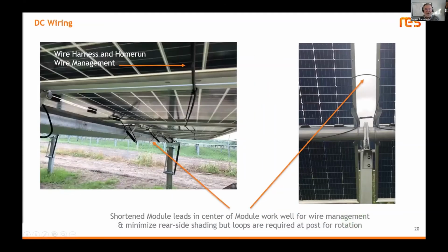There are a couple of pictures that I want to show here. For example, you have to understand the home run, the wire harness home run. Where does it go? Can it go like this on the rear side of a module? Or this? You have to plan for it. There's no room for improvisation. It needs to be validated. The shorter leads, if you have junction boxes, are definitely a benefit, but because you have a moving part, that lead needs a loop at the post, where the posts are, to allow for movement because the tracker moves. So all that needs to be very, very carefully planned for, and that is the impact on DC cabling.